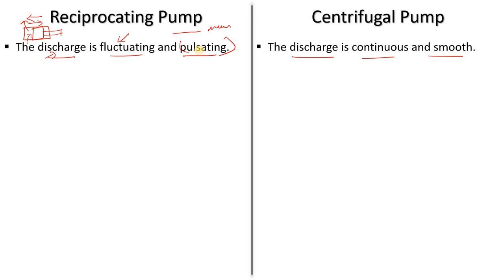To prevent pulsation, a damper is used. We also use a double-acting pump, which has two suction and two discharge pipes. When one suction valve is open, the other's discharge valve is open, making suction and discharge more continuous. In the centrifugal pump, there is no pulsation — as you start the pump, discharge is continuous.